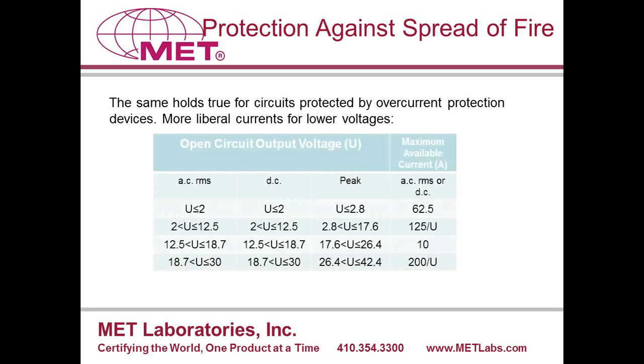For limited energy circuits which are managed by an overcurrent device such as a fuse, the allowable currents for a low voltage circuit are even higher. Going back to the 1.8-volt and 5-volt circuits again, the limit on current when a fuse is present in a 1.8-volt circuit is now 62.5 amps instead of 50 amps. And for a 5-volt circuit, the current can now be 25 amps instead of 20 amps.